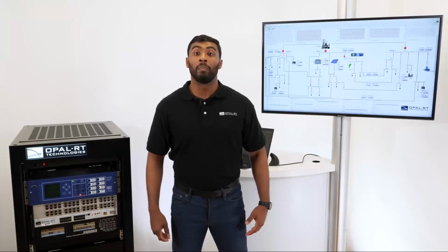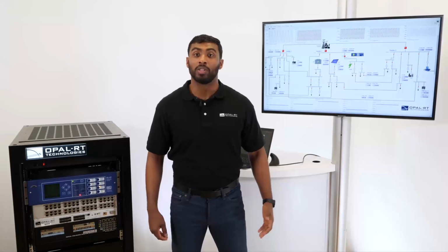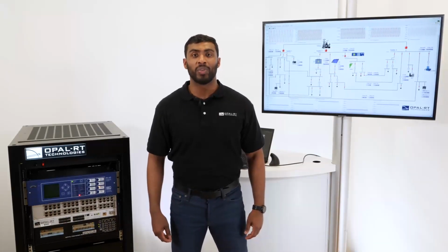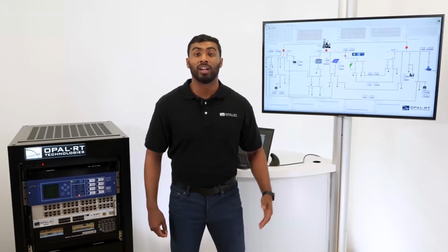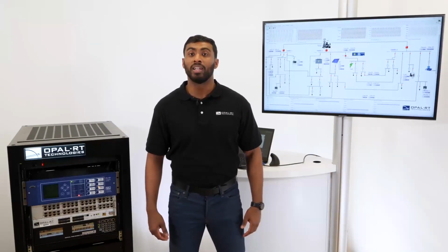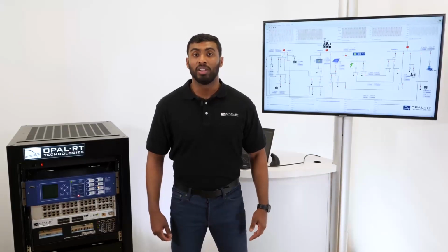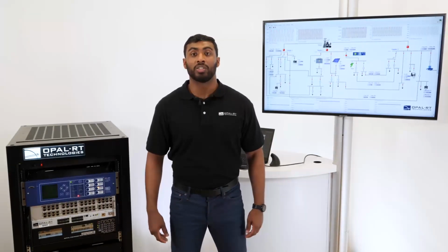Today we saw our microgrid Ghost model running on our HyperSim EMT simulation software. This was running on our 5707XG platform and interacting with the SEL-421 relay by means of analog output. In consequence, the relay was sending a GOOSE message back to the simulator to be able to close the circuit breaker. This shows us a full HIL setup for our protection scheme scenario.